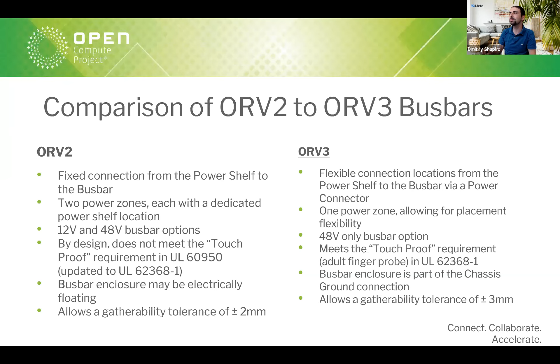The 48 volt version in ORV2 is depicted like this. Some features I want to point out, because they'll be very different in ORV3: look at the front end, the snout with the insulator and bus bars, and how close the bus bars and snout are to the opening of the cage itself. Also the gatherability is fairly simple, pretty much just an angular gatherability. These are some of the areas that will change in ORV3.